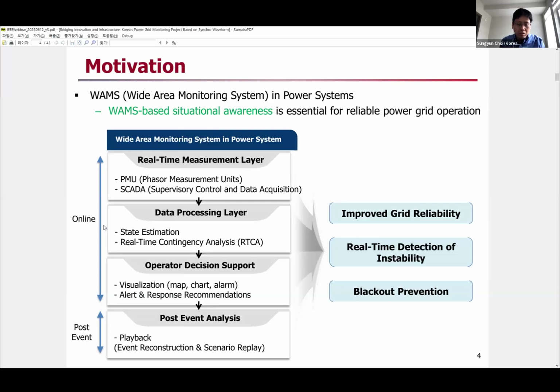Historically, the data is captured, measured by the magnitude. I mean, the power system is an AC system, so the voltage and current data are sinusoidal. A long time ago, those data were captured by magnitude, but it is difficult to measure the angle. The AC waveform has magnitude and phase angle. So that's why the PMU was introduced, to measure magnitude and phase angle as well, based on GPS synchronized signals. So PMU and SCADA are widely used measurements.